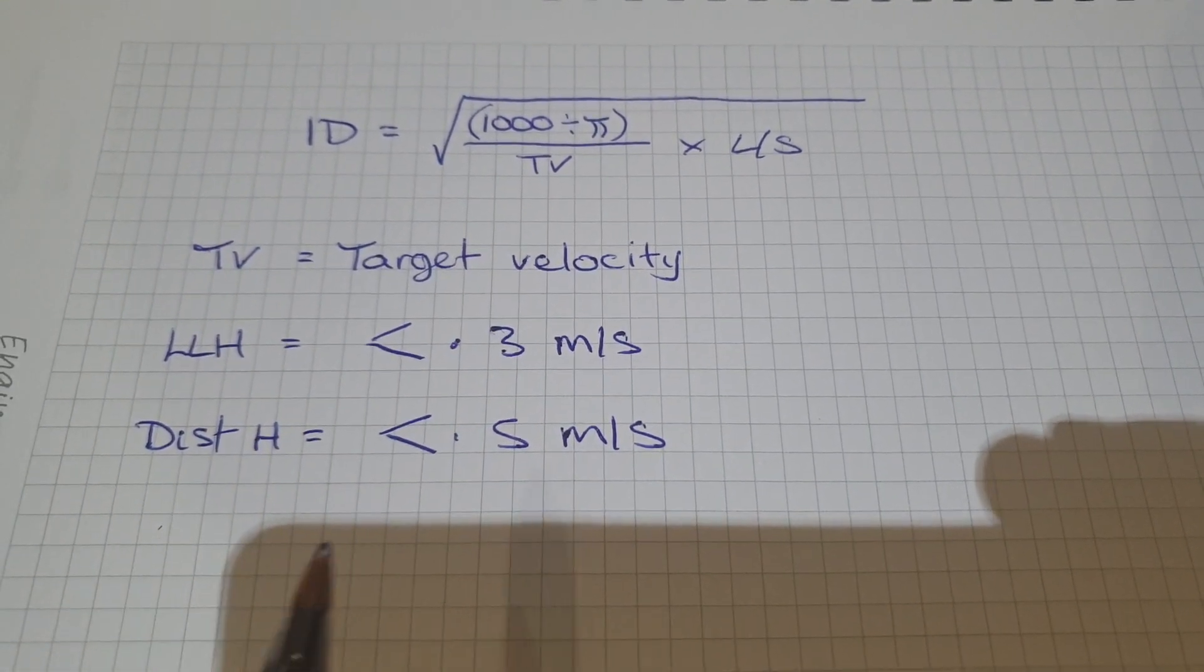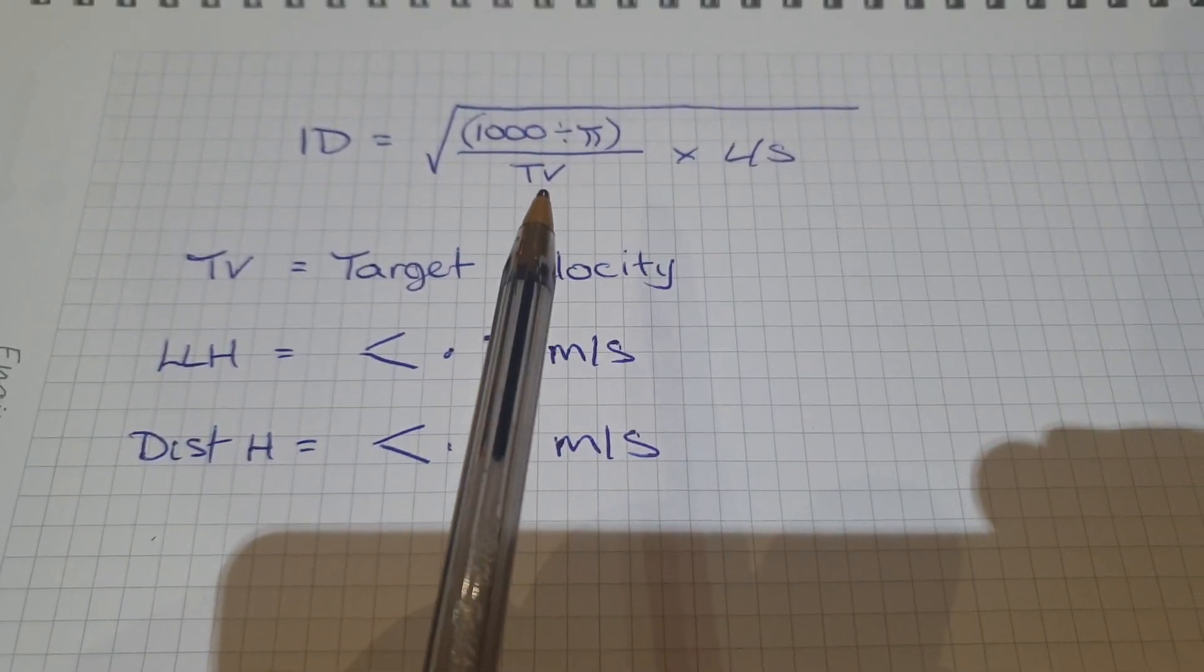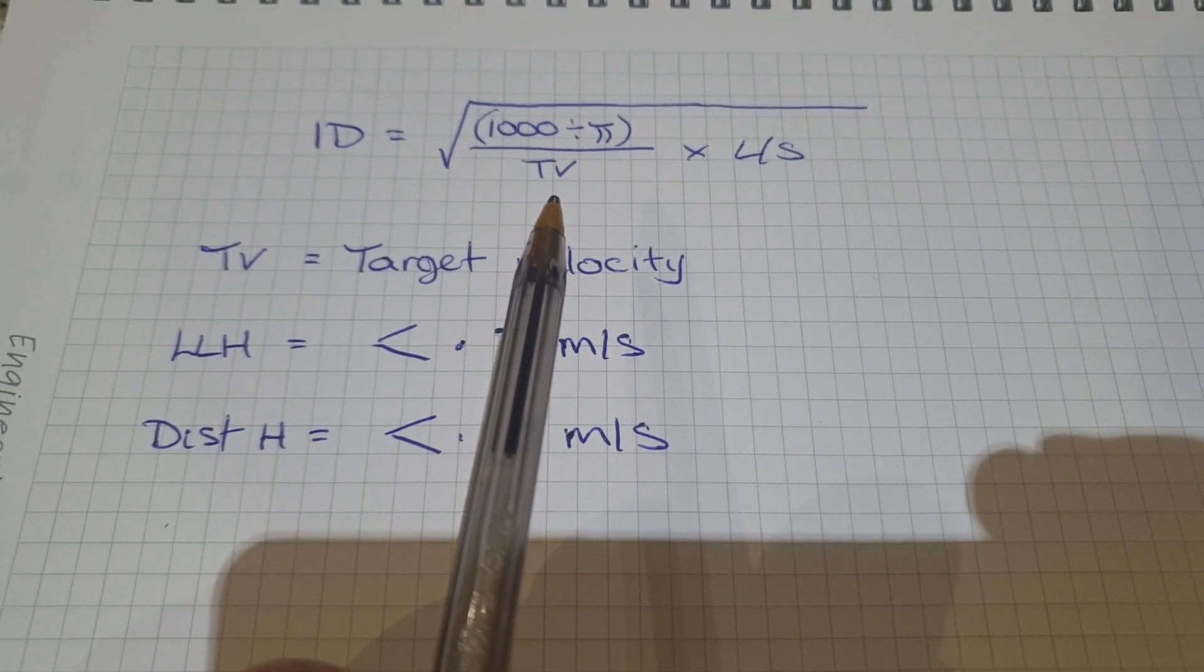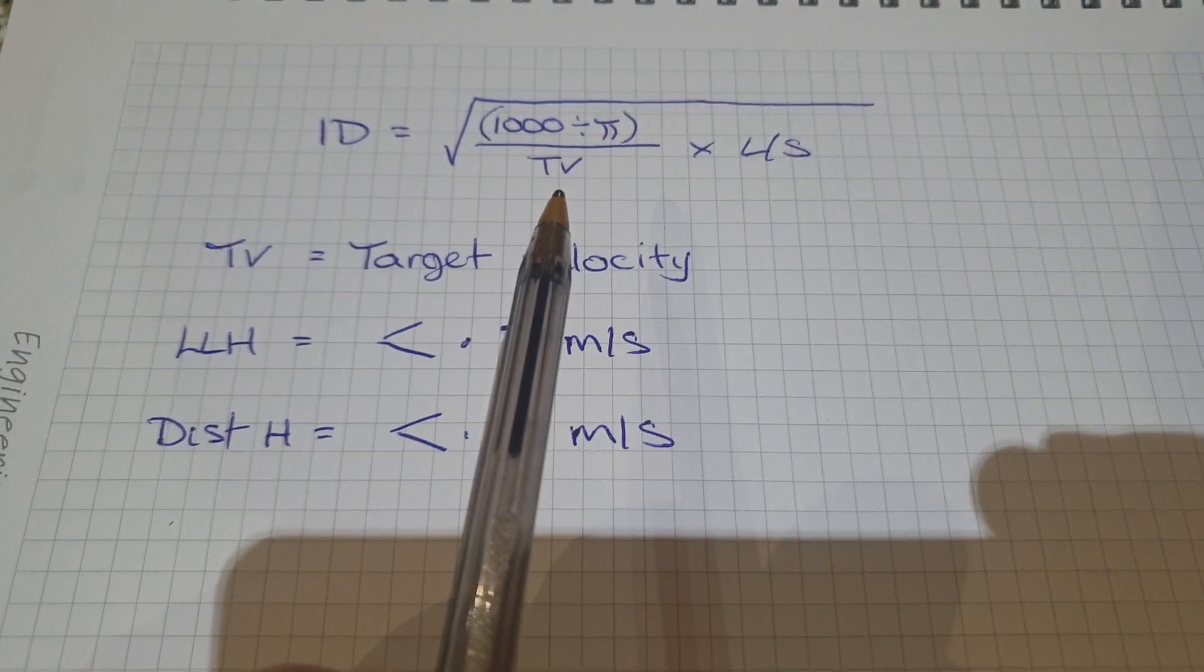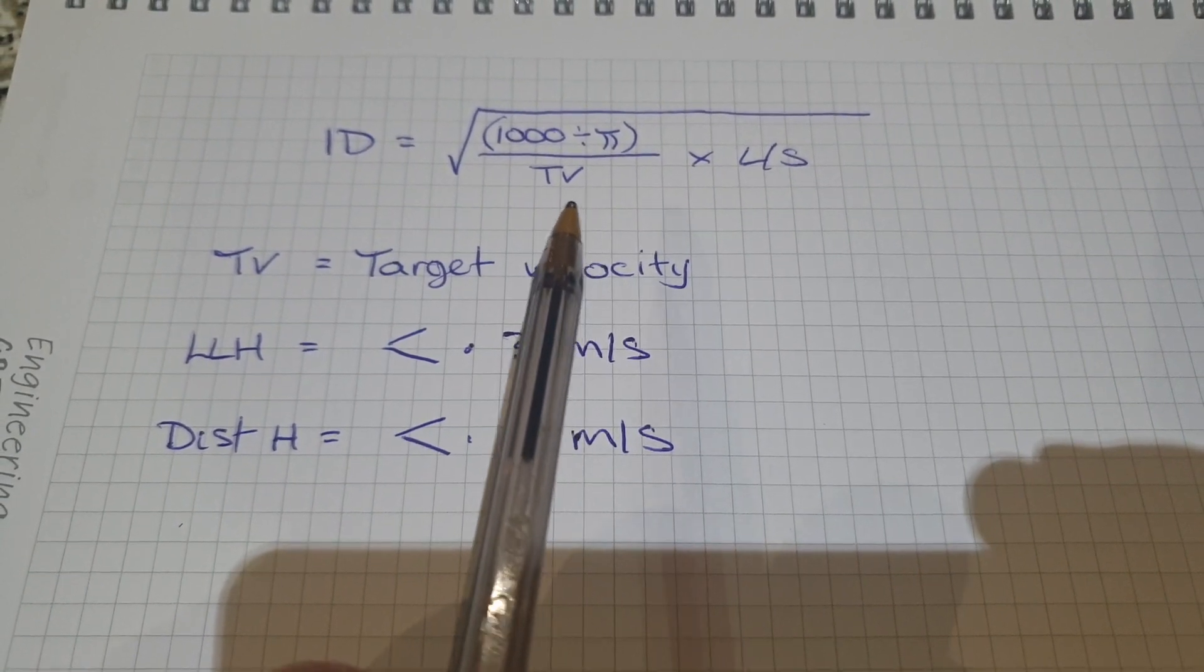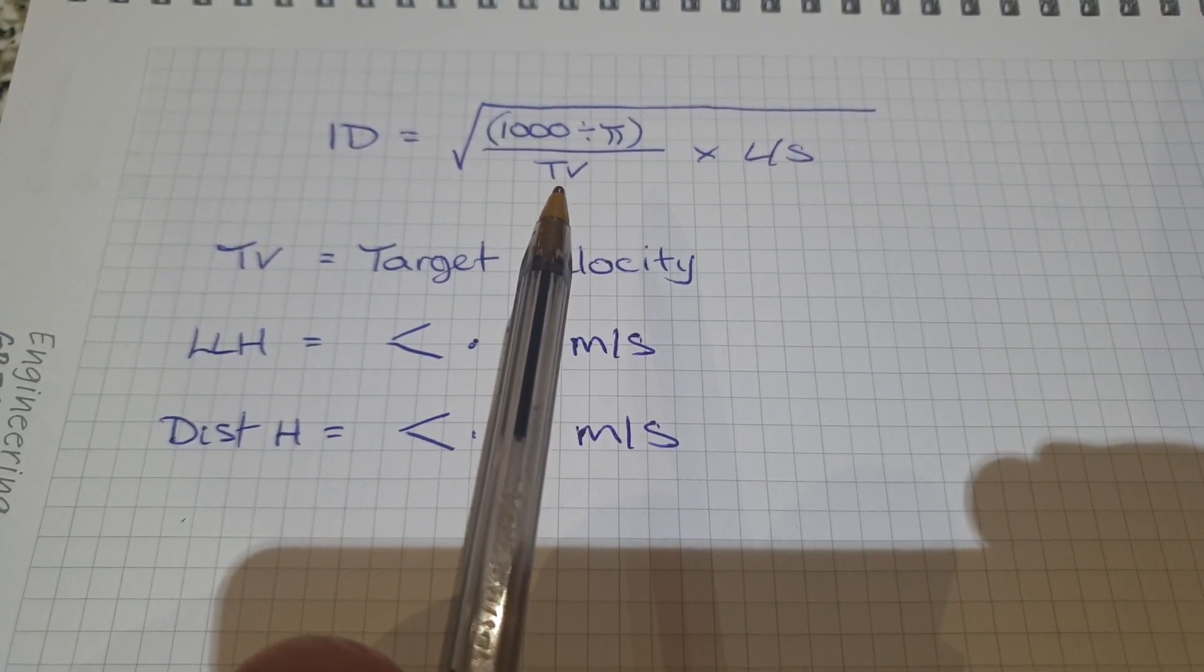For heating pipes, by the way, which I haven't loaded here, the target velocity is 0.9. Some sources claim or state 1 meter per second. Simply in the design book put 0.9, and I've seen it used very commonly to use the value of 1 meter per second.